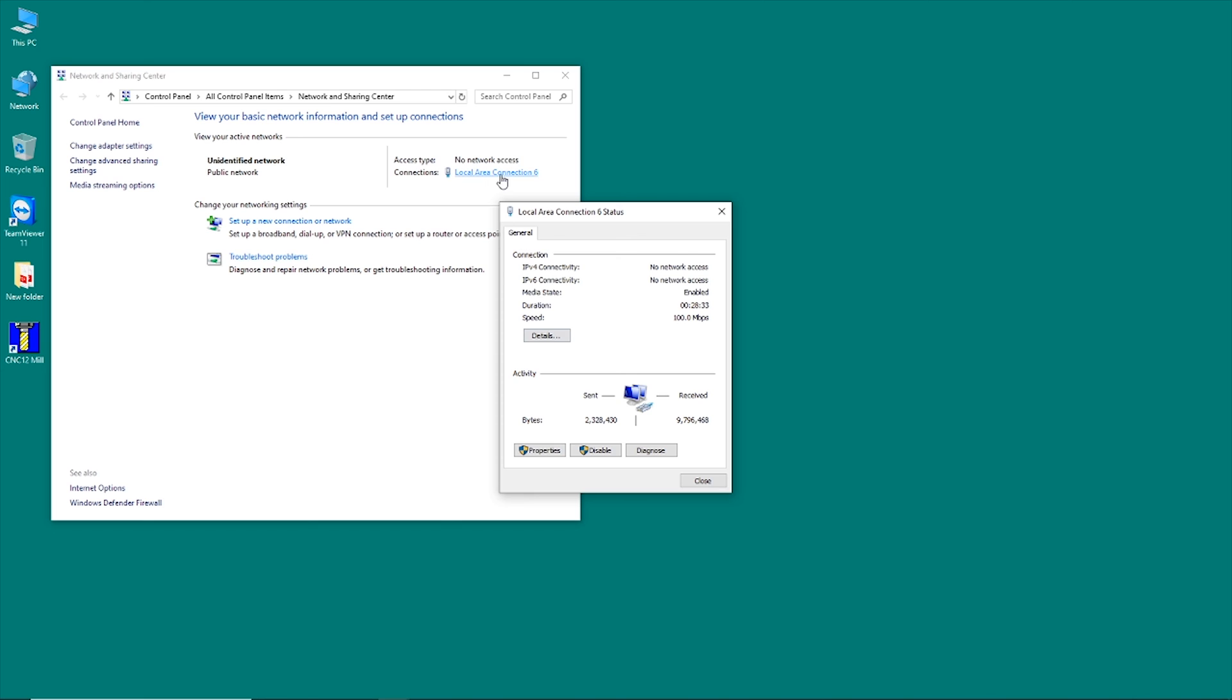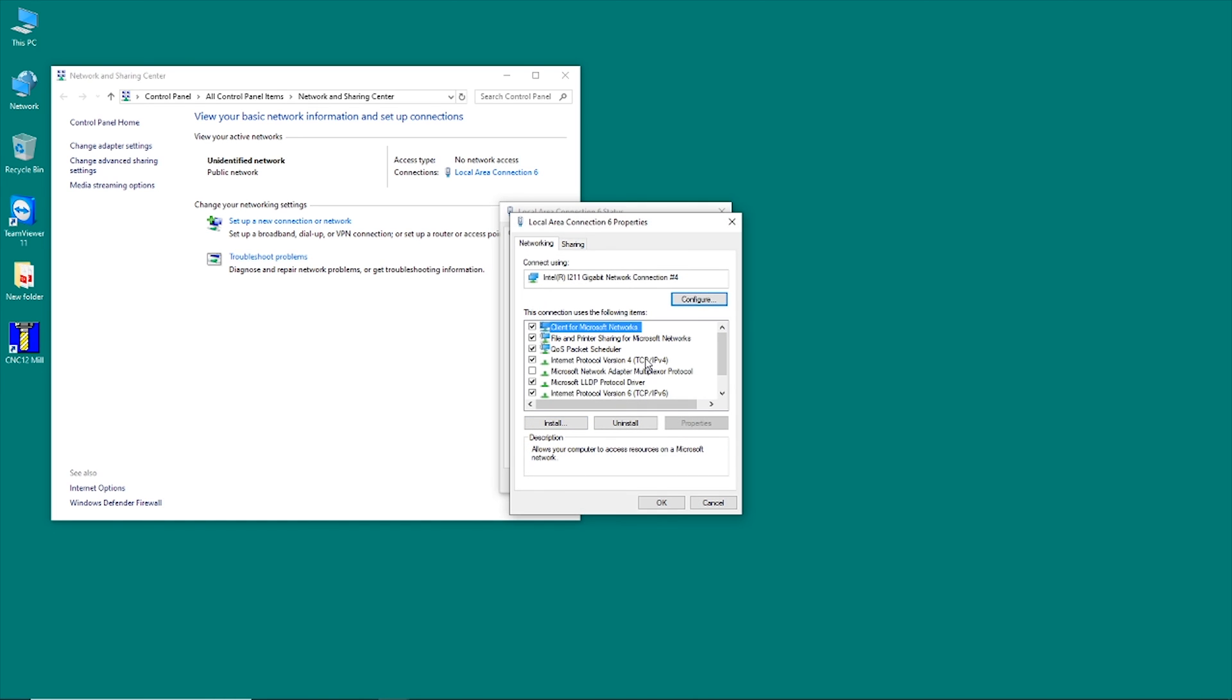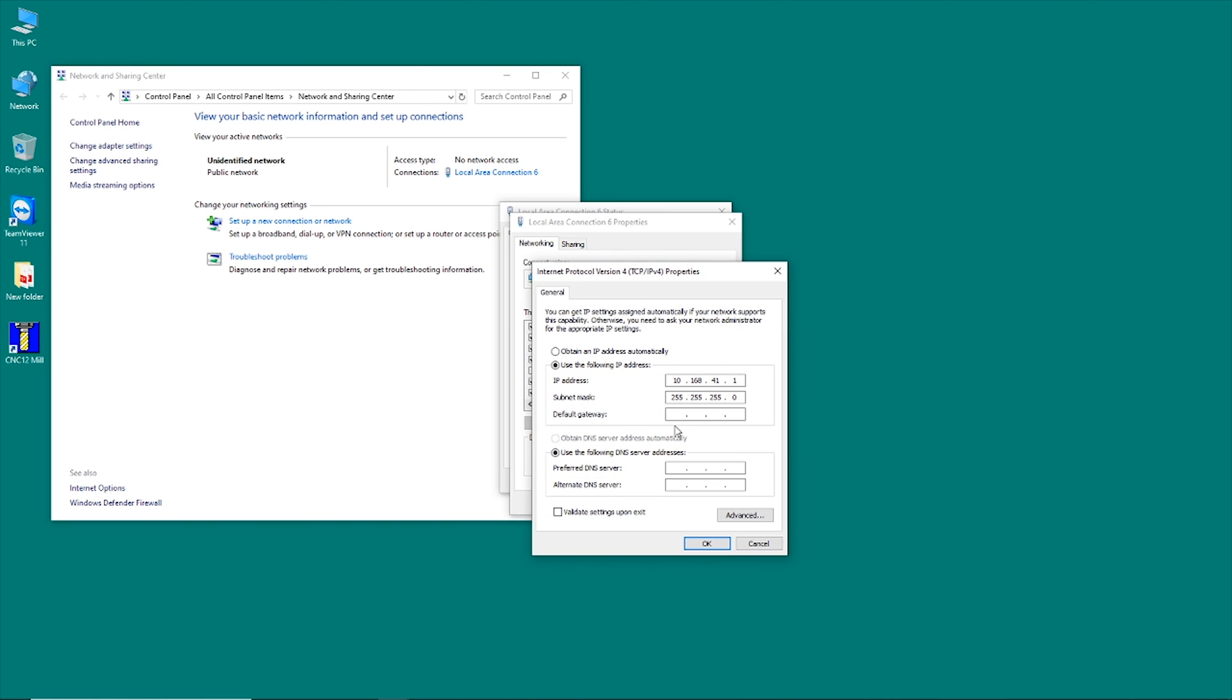So if you click on that, go down to properties. And then what you want to do is scroll down here until you see the internet protocol version 4 TCP IP v4. You don't want the v6, you want the v4. Highlight that and then go to properties. And you'll see here, where the setup software has actually given this a static IP address of 10.168.41.1. And that's what you need to have in there for the computer to be able to successfully talk to the Acorn. So if that's not in there, you can set this manually just by changing from automatic to dedicated and then go ahead and enter these values.